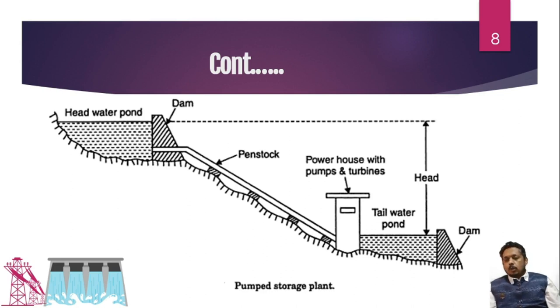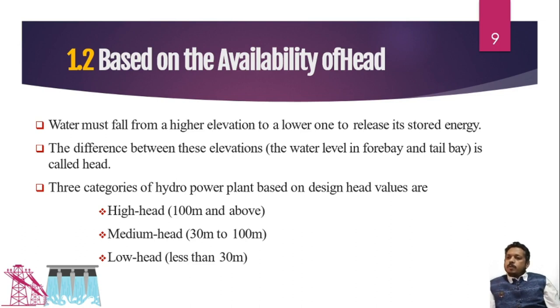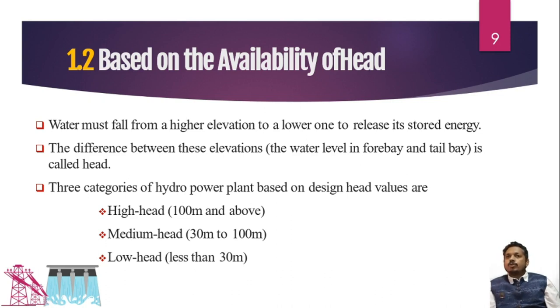The second category of analysis is based on availability of head. Head means the slope distance between our reservoir and the turbine — the distance between these two points is called the head. We have three types of power plants based on head: high head, where the distance is more than 100 meters; medium head, with 30 to 100 meters; and low head, with less than 30 meters. The force of the water at the turbine is defined by this head.